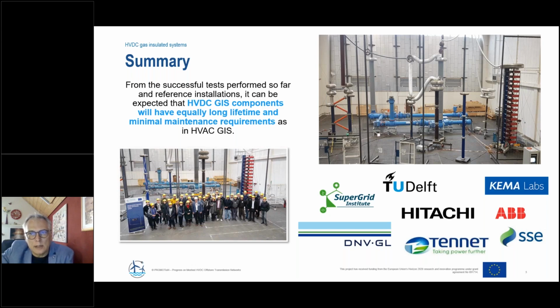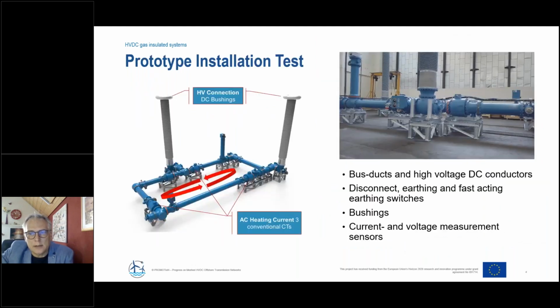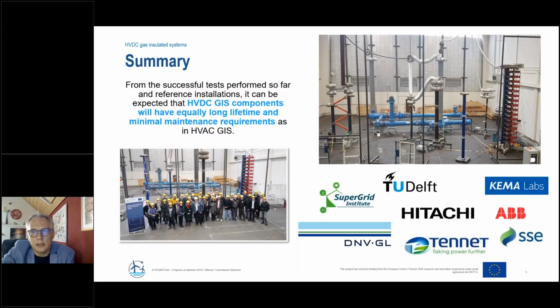Maybe most of you know that a gas insulated switchgear has some advantages compared to air insulated switchgear, and that is mainly related to the size. A gas insulated switchgear could be installed with a much higher degree of compactness, and we can say that we can reduce the size of the HVDC switchgear using gas insulated components by 70 to 95%, and that is of course very interesting for platform installations where the size is the main restriction for use of switchgear components.